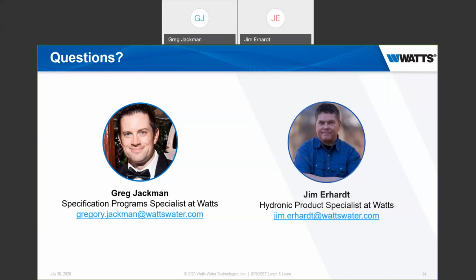Is the valve easy to be cleaned or serviced? Are there replacement parts for internal components? There are no internal replacement parts right now. But again, if it's suspect that the system has debris, if it's an old retrofit system, we do recommend in the installation instructions that for retrofit applications something like the Watts 777 Y strainer be used upstream of the valve. Is there an option for the material of the gauge face? No, there is not.